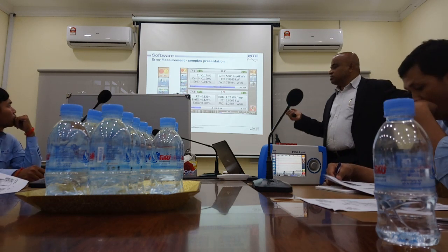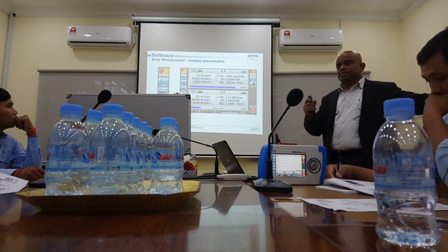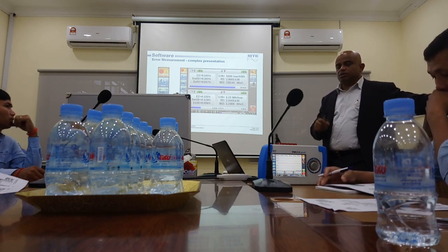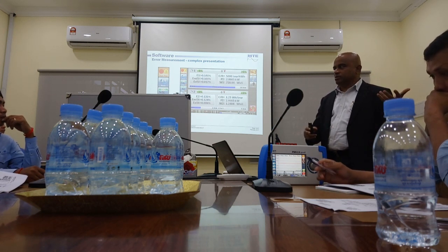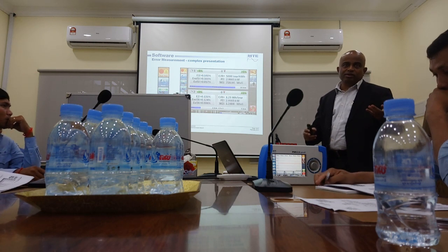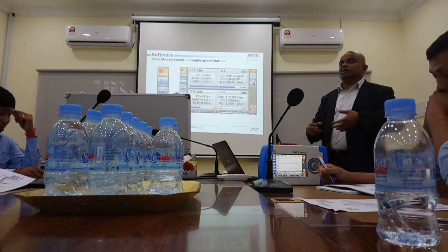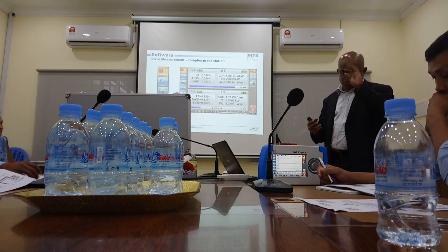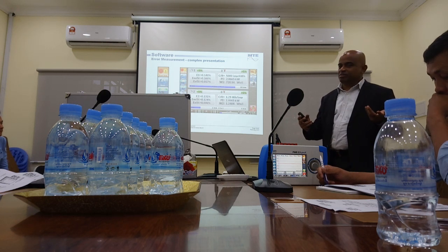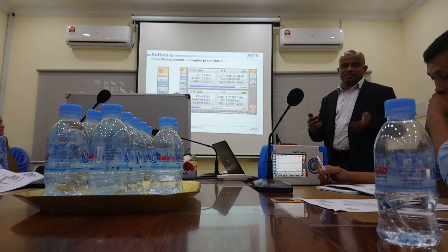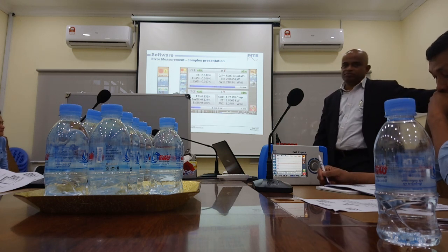Why all this flexibility is there is because sometimes you do testing in the laboratory very easily because you can control the voltage and the current, but when you go to the field sometimes you cannot touch the customer load. You have to test with the customer load. So if the customer has very high current, then it is very easy. The pulse comes very fast, you can finish the test very fast. But if the customer has a very low load, it is very challenging because you need to wait for very long.